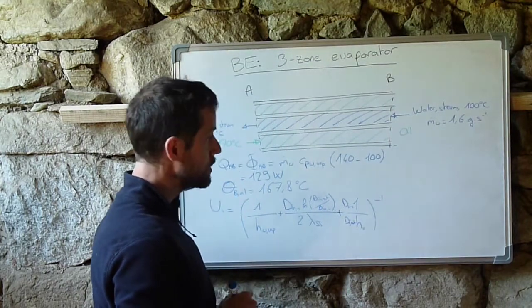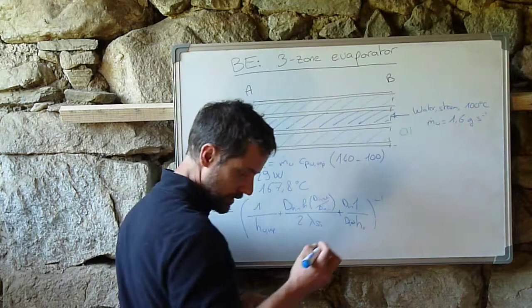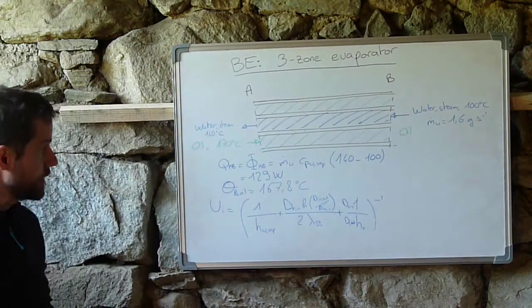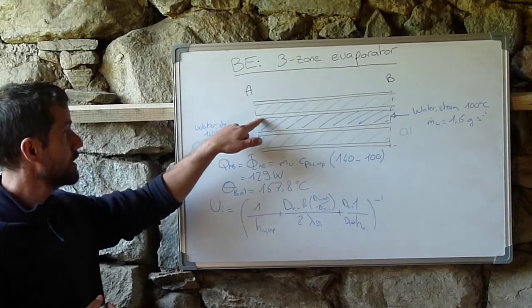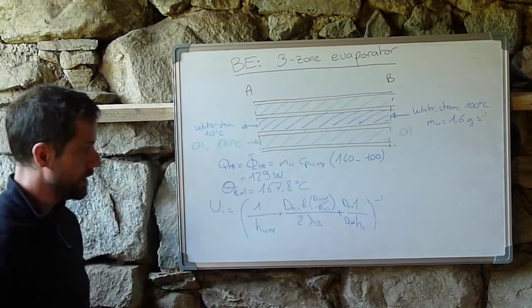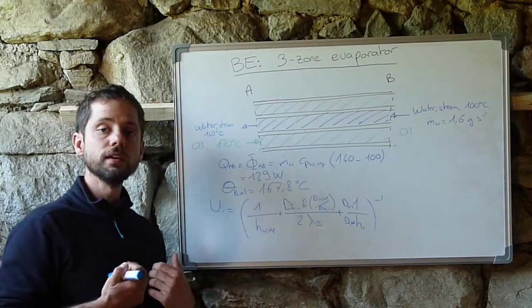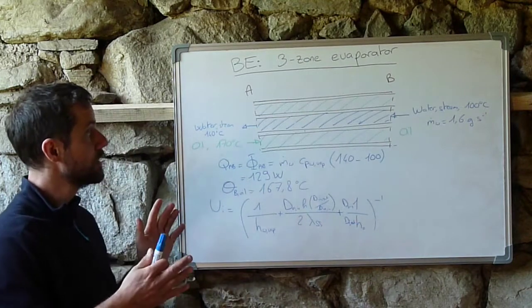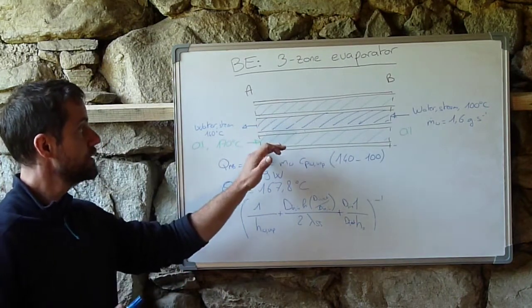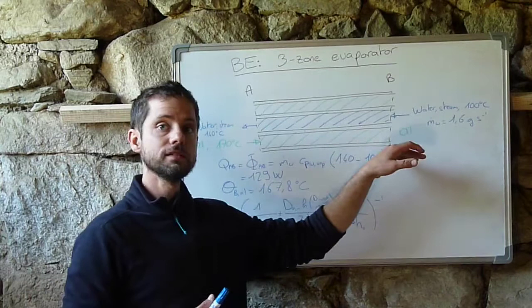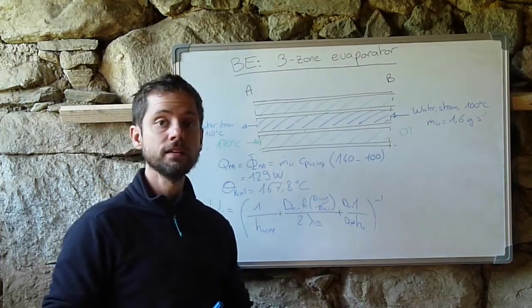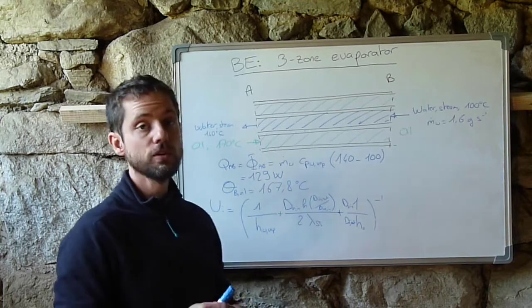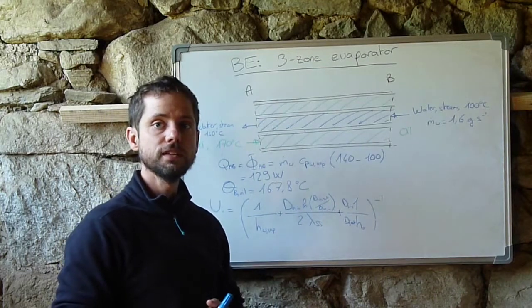And then you use this to calculate the heat transfer area at the internal part, so AI. And you can use this to calculate then the length that is needed for this section of the double pipe heat exchanger. You do it for each of the sections and then you can have the global design for this heat exchanger.